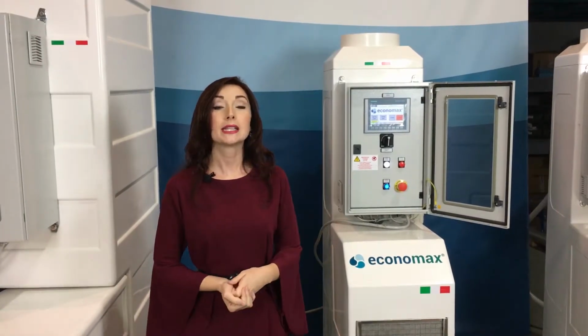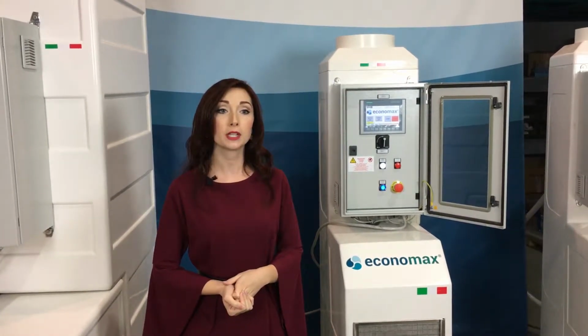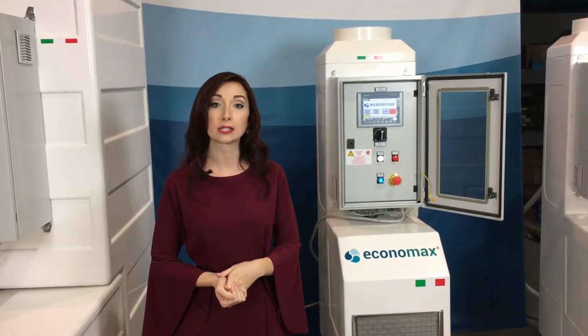The cooling tower is the most efficient and most common machine for cooling return water from industrial plants. This happens because the tower is able to lower water temperature by circulating it and making it reusable for the cooling of the machines, simply using the natural principle of evaporation. The cooling tower that we present to you today is in fact a green machine, thanks to its high efficiency, its very low energy consumption compared to a normal refrigeration cycle, its water-saving aspect, and its minimal acoustic impact.